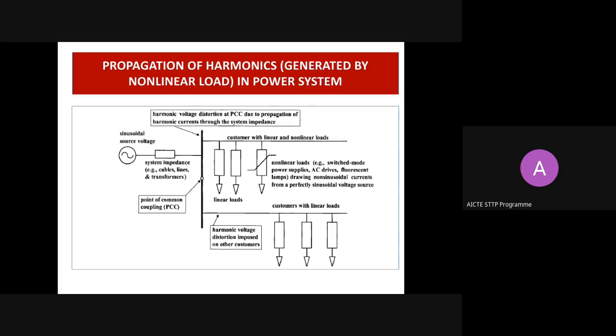That's why at the point of common coupling, the PCC, the utility has to see that the voltage is not disturbed by the poor power quality of the non-linear loads present in consumer premises. That's why every consumer has to ensure their harmonic current does not exceed a certain limit. We have to fix the limit on harmonic current at the customer premises, so that non-linear loads do not draw excessive harmonic current from the grid, which has an impact on the voltage. As a utility, they have to put appropriate devices at different locations to ensure voltage is delivered to all consumers without harmonics present in the system.